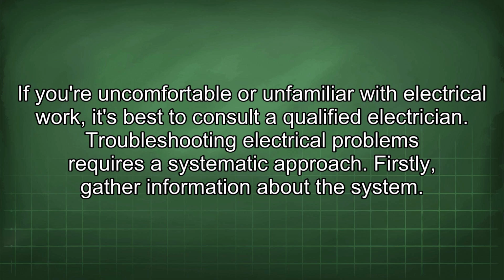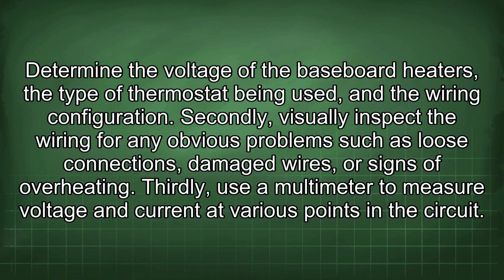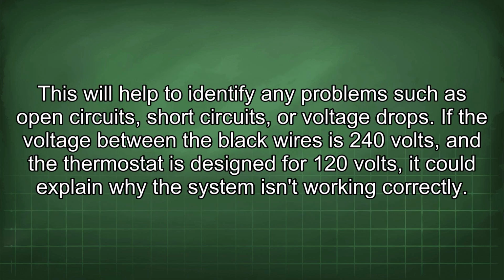Troubleshooting electrical problems requires a systematic approach. Firstly, gather information about the system. Determine the voltage of the baseboard heaters, the type of thermostat being used, and the wiring configuration. Secondly, visually inspect the wiring for any obvious problems such as loose connections, damaged wires, or signs of overheating. Thirdly, use a multimeter to measure voltage and current at various points in the circuit. This will help to identify any problems such as open circuits, short circuits, or voltage drops.